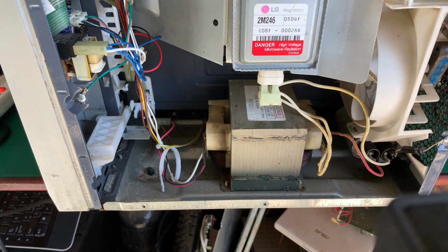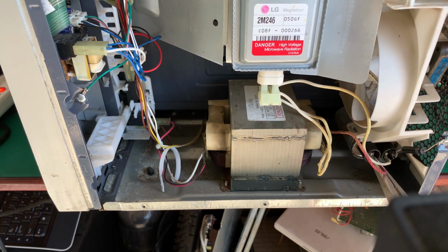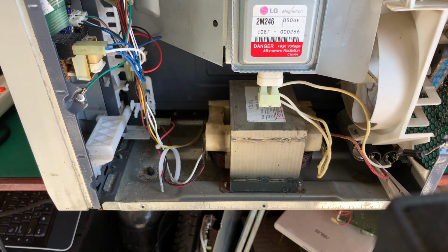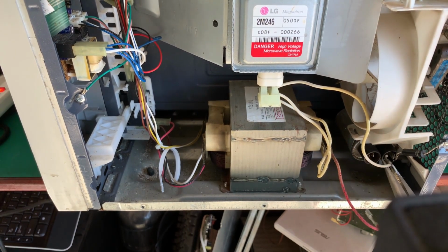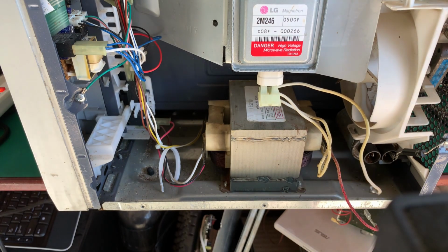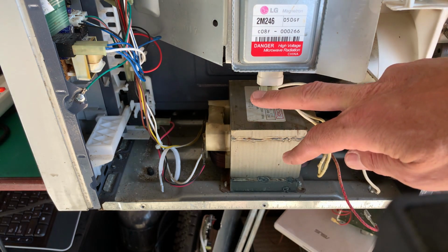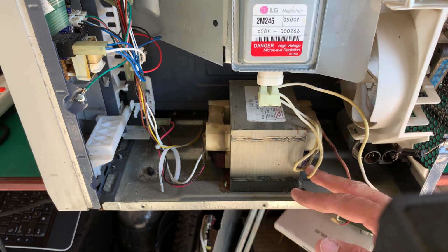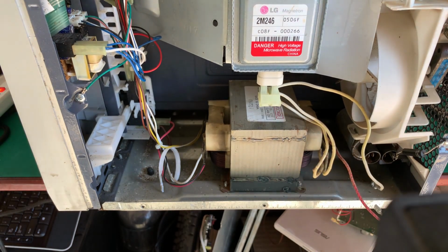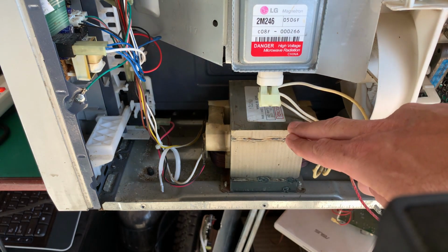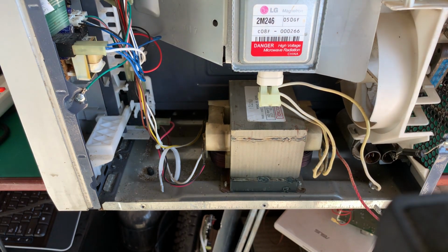Of course, if you're scared like me, and I have a very healthy respect for high voltage. You notice I'm using my long nose pliers just to pull these wires out, because I really don't want to be touching things, even though I know it's safe and I know it's off. So what I'll do is I'll just pull this out, and we can now see that yes, that is our secondary side. We can measure the secondary side of our high voltage transformer, and we can measure the magnetron, and we can measure this capacitor. So let's just get that set up.